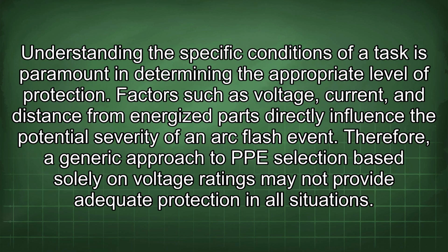Understanding the specific conditions of a task is paramount in determining the appropriate level of protection. Factors such as voltage, current, and distance from energized parts directly influence the potential severity of an arc flash event. Therefore, a generic approach to PPE selection based solely on voltage ratings may not provide adequate protection in all situations.